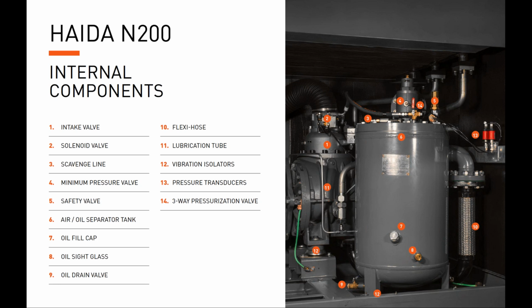One is for the main line pressure, and the other one you can see the pressure drop across the air oil separator filter, which will let you know when to change the filter. Another service bonus is the three-way pressurization valve, which allows you to keep pressure within the air oil separator tank when you go to change the oil. So you can have pressure in the tank, which allows you to expel the oil a lot easier.